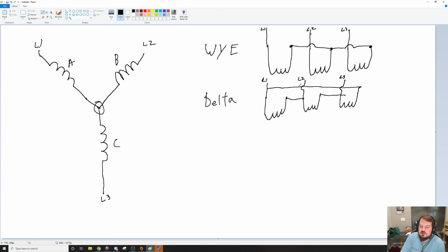In a delta, they are one side, so A is connected to B and C, and B is connected to A and C. They're connected in a loop. So you can start at one spot, go through A, go through B, go through C, and go back to A. That's the difference, and that's what most of this Transformers test is going to be about, identifying Y versus delta.